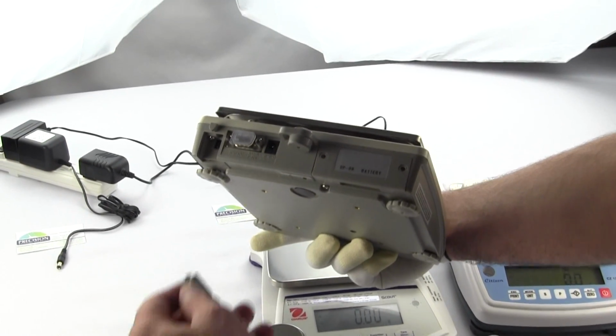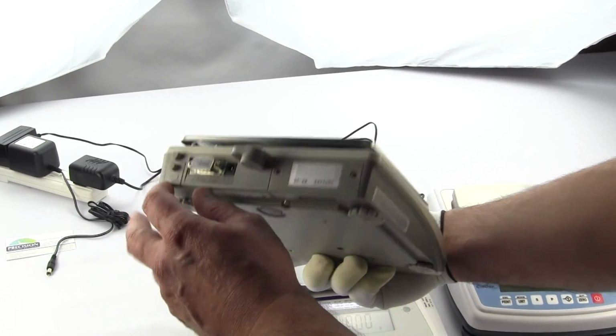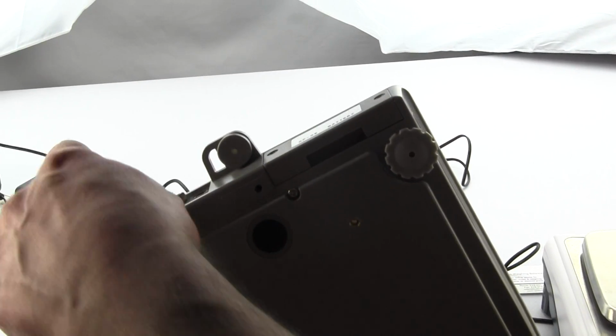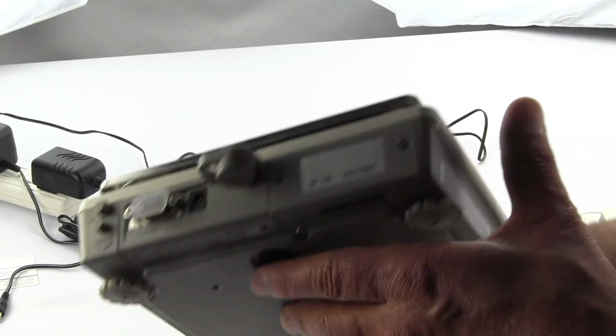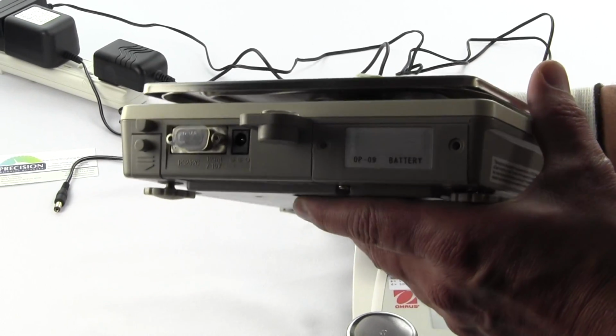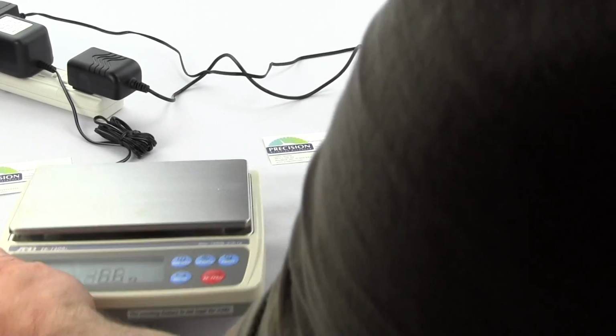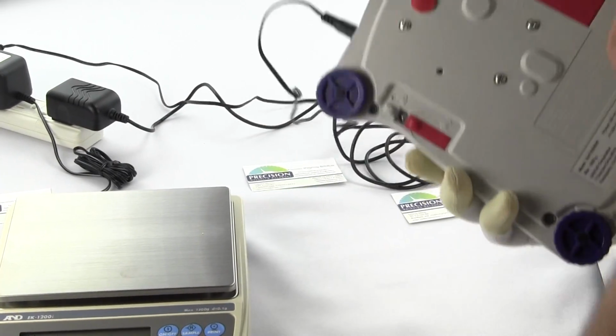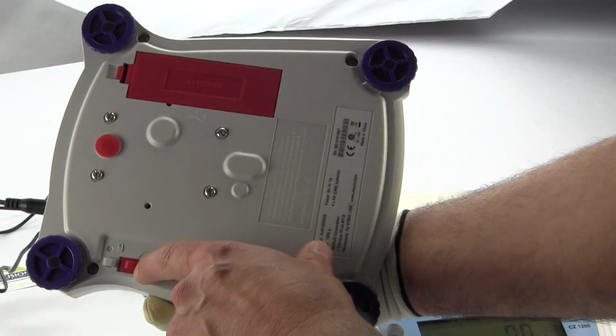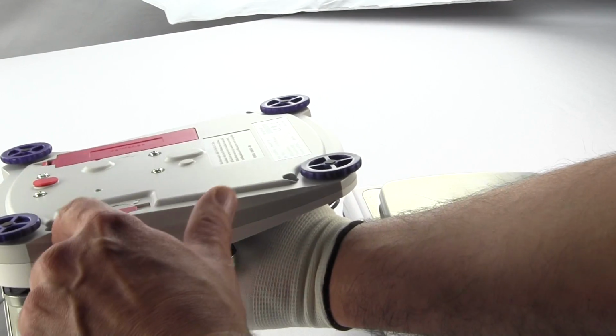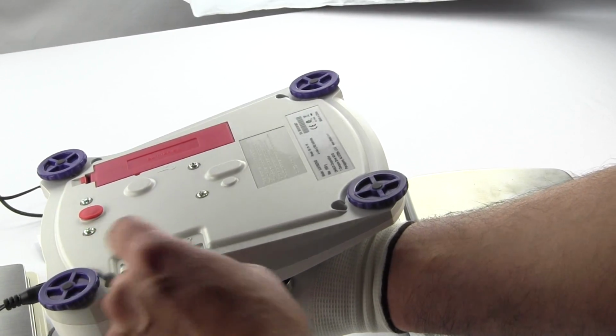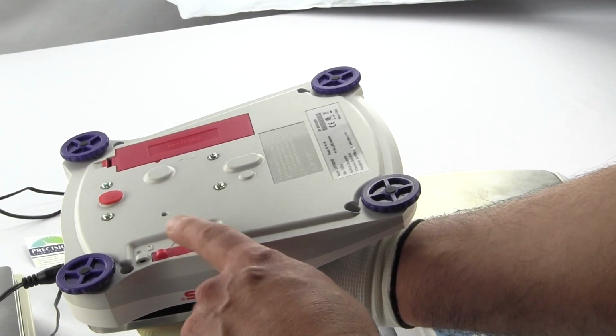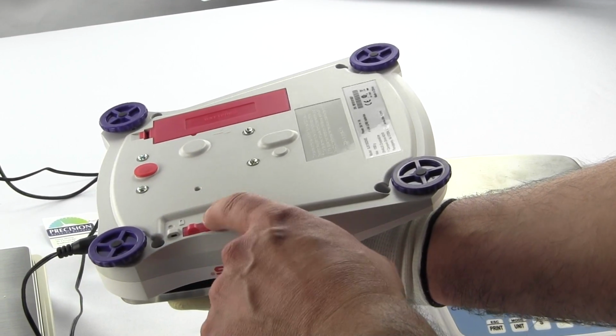Let's talk about lockout real quick. For the A&D, since these scales have to be locked out, Weights and Measures would put this cover on. They stick a wire right through here and they would crimp it. So this is on the Ohaus, very easy to lock out the scale and put it into the legal for trade mode. On the Ohaus, again, there's a switch right here. They literally will lock it, and they would put a cable right through here and they would crimp it. Or they put a sticker right across here. So if you try to take it out of the lock mode, they could definitely tell.